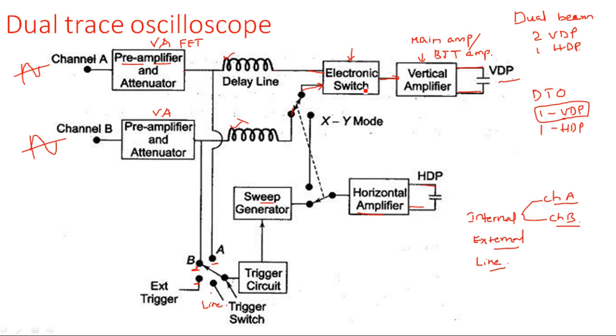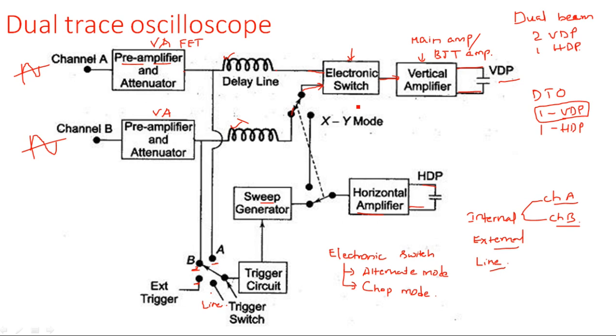The electronic switch operates in two modes: alternate mode and chop mode. The purpose of the electronic switch is to select Channel A and Channel B continuously or alternatively, so that whenever the switch is connected to Channel A, Channel A is displayed on the vertical deflection plate, and whenever connected to Channel B, Channel B is displayed.